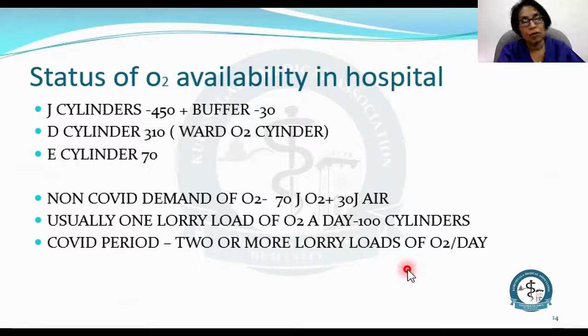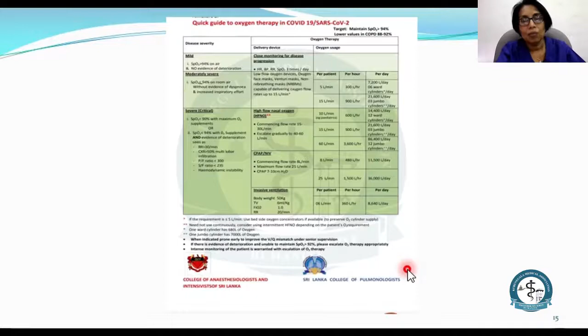In a non-COVID period, oxygen demand is 70 jumbo cylinders plus 30 air cylinders. Usually, 1 lorry load of oxygen a day is provided to this hospital, which carries around 100 cylinders per day. In the COVID period, 2 or more lorry loads have to be provided per day. So you can imagine the demand for oxygen on this hospital. Again, it tells you how much oxygen is used.